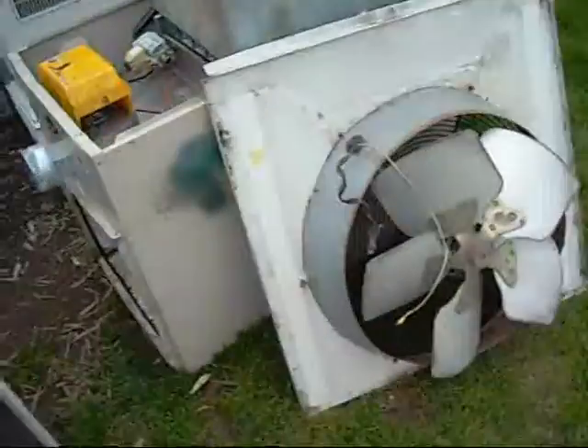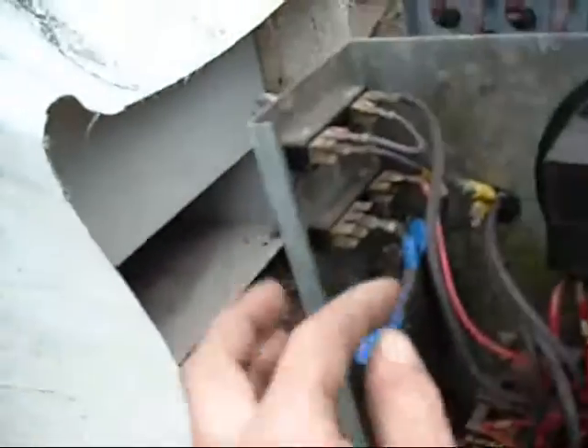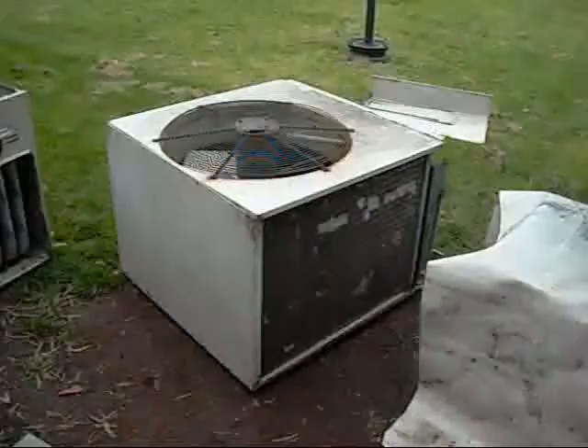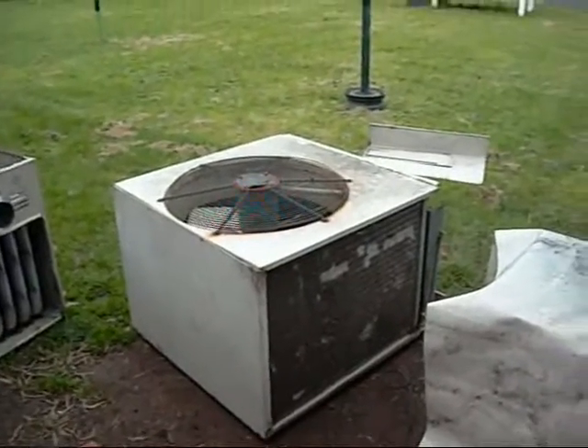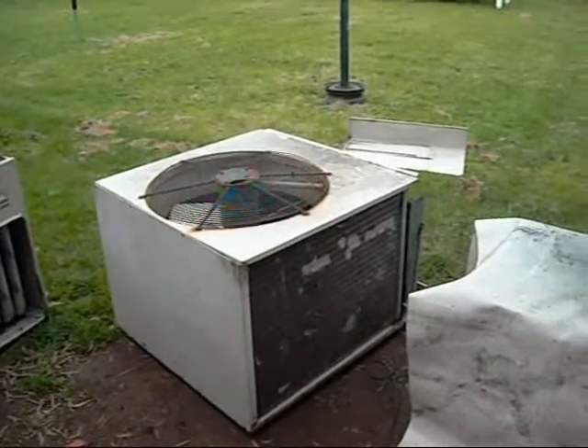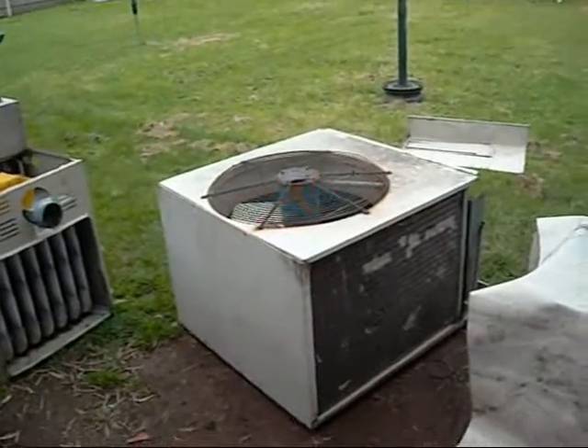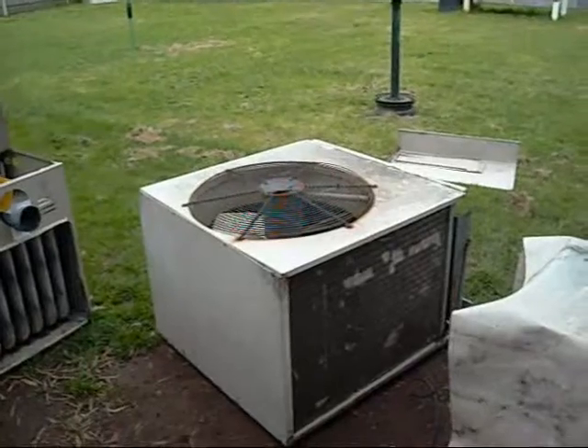I'm going to put the top back on and see if the fan still works. I've hot wired these blocks here so that they just supply the fan. I'll isolate all this control stuff. The contactors are ancient. A lot different to the new ones. A quick test of the condensing unit fan. I think it's a 2/3 horsepower motor, but definitely single phase, 240 volts.